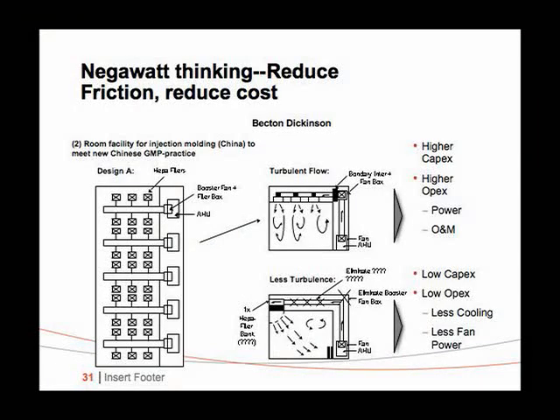Let's construct a huge filter bank and create unidirectional flow, which will be cleaner and much less pressure drop. And let's not put in all these booster fans. The savings in ducting and booster fans pays for the extra filters, which have less pressure drop, so on a life cycle basis, and in first cost, it is cheaper and better.